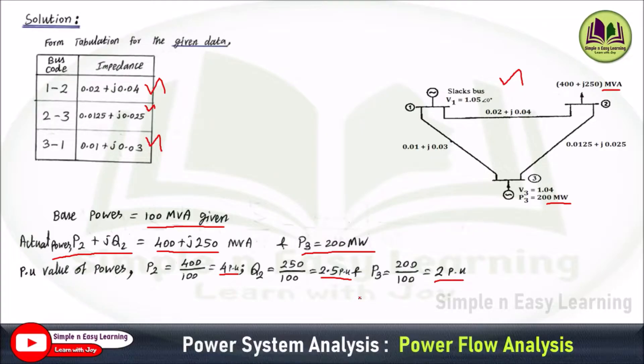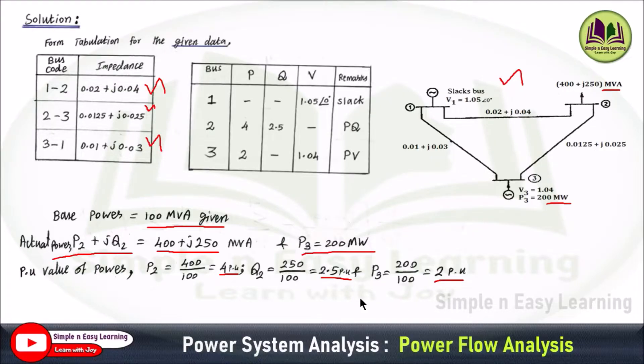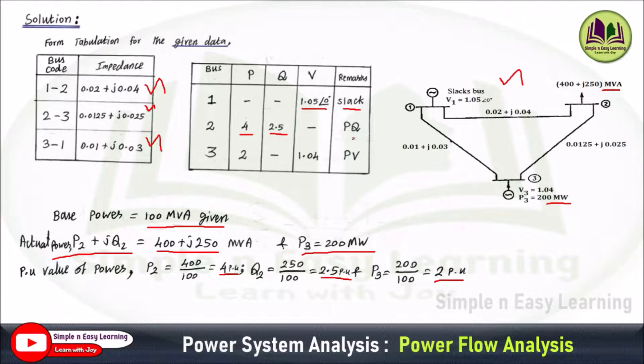Now we draw the bus data tabular column with three buses: bus 1, 2, and 3. From the diagram, the first bus is a slack bus with voltage 1.05 and angle 0 specified. The second bus is a load bus — P and Q are specified as 4 and 2.5 per unit values — it is a PQ bus. The third bus has real power and voltage magnitude specified — it is a PV bus, also called a generator bus.